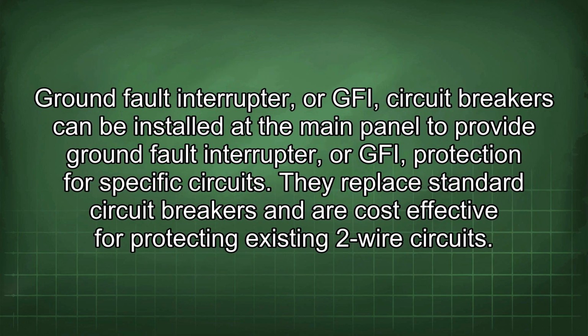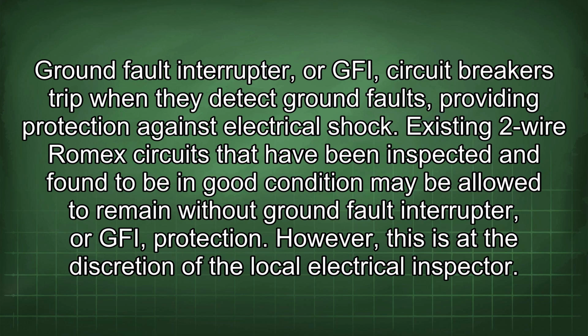Ground fault interrupter, or GFI, circuit breakers can be installed at the main panel to provide GFI protection for specific circuits. They replace standard circuit breakers and are cost-effective for protecting existing two-wire circuits. GFI circuit breakers trip when they detect ground faults, providing protection against electrical shock.